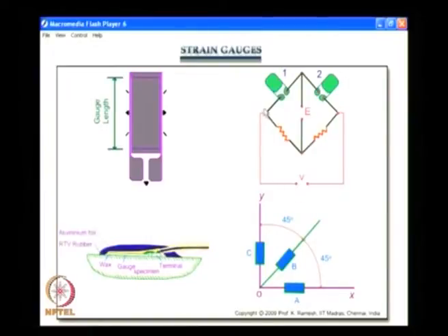Here I have a Wheatstone bridge shown, and this also has two strain gauges connected, in a half bridge configuration. In fact, this is the most celebrated one because it also has temperature compensation provided, when these two strain gauges are representing the point at the model of interest, and the one which is also kept at the same temperature, so that any temperature effect happening at the specimen is compensated by the second strain gauge.